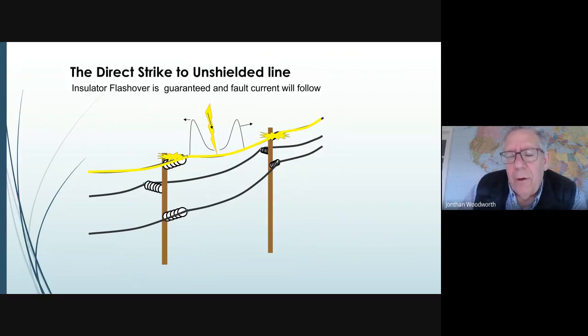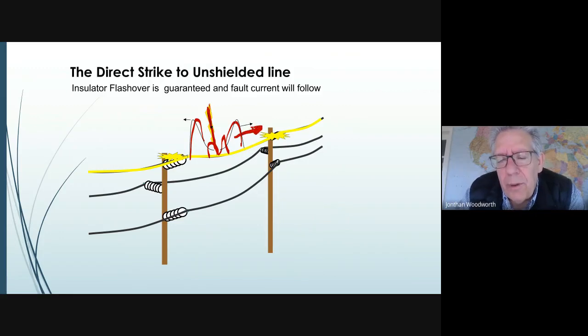The other thing I didn't mention here is something called traveling waves. I demonstrated it, but we didn't actually talk about it. When lightning hits a line and generates a voltage surge, that surge actually travels down the line at very close to the speed of light. Whether it's a shield wire or a big phase conductor, it travels close to the speed of light. If there is no shield on a system, this surge of 1,000,000 volts will flash over these insulators. So it's this traveling wave that causes us a problem. Well, it's part of the process that causes a problem. First, you have a strike, and then it travels in both directions.